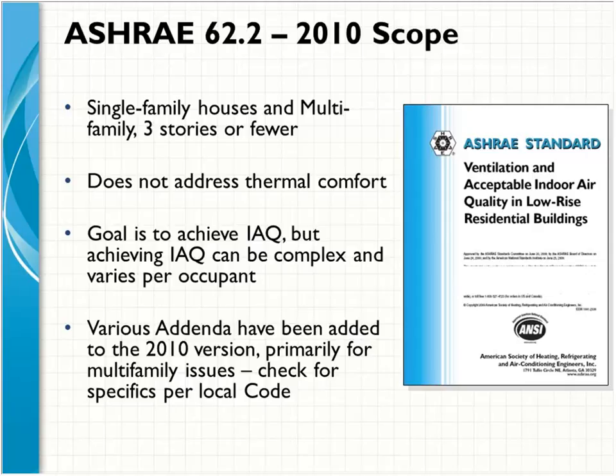Very good. All right, so ASHRAE 62.2, we used to actually have to buy a manual years ago, but of course all this information is available online now. That gives you a little date on myself, but we used to actually have to buy a manual every time it was updated. The ASHRAE 62.2 code refers to single and multifamily properties up to 3 stories, but it does not address thermal comfort. This is strictly air exchanges. We're not talking about a Manual D or a Manual J here and getting the right number of BTUs in each room. This is just referring to the ventilation component.